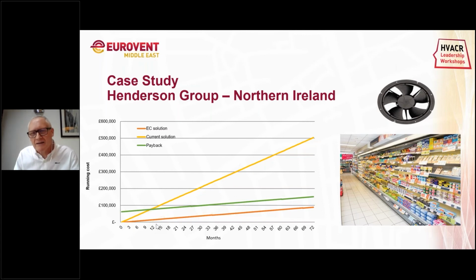One interesting fact is that when the contractor changed the fans, they needed adapter plates on only 15% of them. Out of 2,000 fans, only about 15% needed a small adapter plate, which was just a small metal plate punched out. The wiring was exactly the same - you put 240 volts straight onto the ECM, so there was no extra wiring needed in this particular case study. So, a great case study.